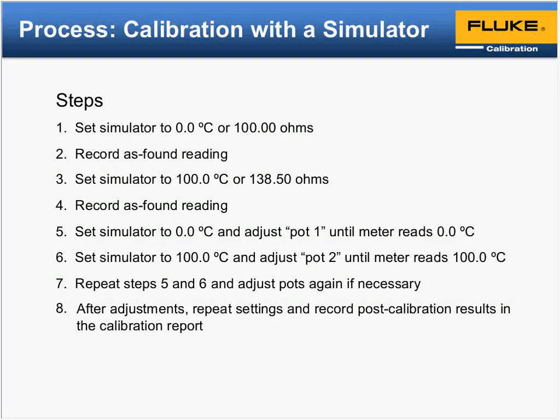So basically, when we're saying traceable, we're proving an unbroken chain that can be taken all the way back to NIST. In this example, we broke our unit under test and are only simulating half the system. So in order to make it completely NIST traceable, we would have had to include that probe somehow. So to address that third bullet point, what would we need to do to make the entire system traceable is to include the probe. And so as we move forward here, we'll talk more about including those, or that last bullet point.